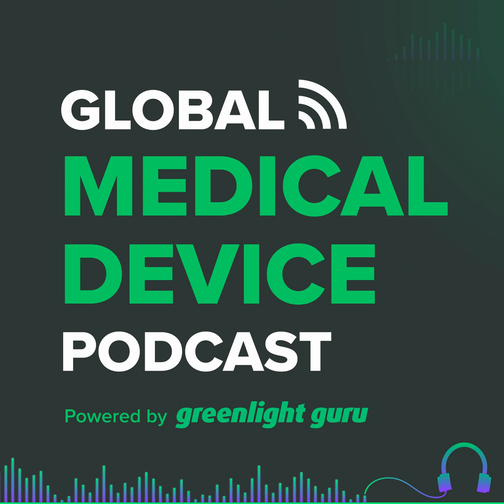Yeah, I can do that. First off, it's not just guidance documents that's built into it. We've built in a lot of IMDRF documents into it as well, as far as the attachments go. And I can talk about the history on how eSTAR came about to be the way it is in a PDF and so on, if you would like later. But when it comes to the guidance documents, we build those in as the guides. So you have the reprocessing guidance document, you have software, EMC, wireless, labeling, you've got all these different guidance documents.